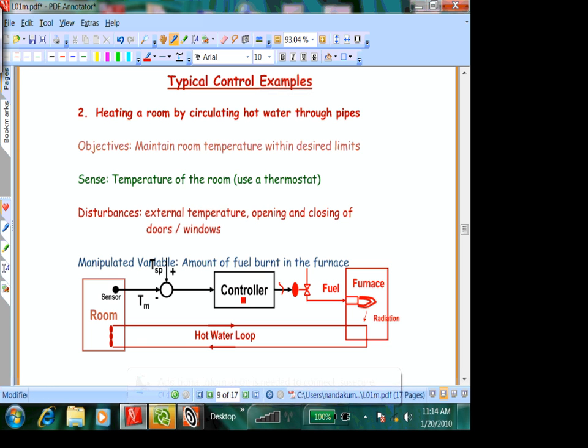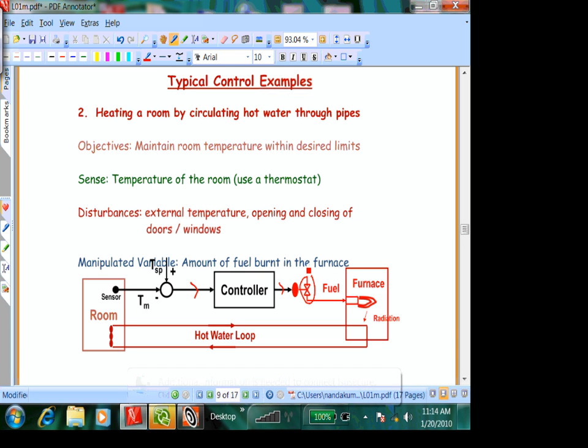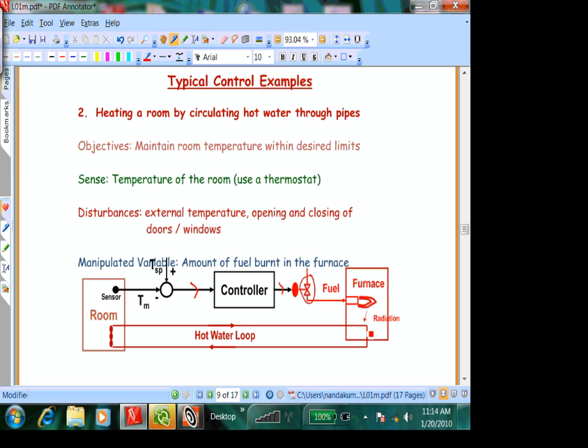These signals could be voltage coming in, and what comes out is so many BTUs per hour. So the controller figures out that a voltage of 5 millivolts corresponds to a temperature difference of 3 degrees, and it does the calculation using the process model and says, okay, I need to send 500 BTU per hour to bring back the temperature by that 3 degrees. So that action goes to a control valve. That means you need to increase the fuel rate. You need to burn more fuel. That will also have its own dynamics. Then the fuel goes into the furnace, and in this case you have a hot water loop. So the hot water temperature goes up, and the heat is delivered to the room. That completes the cycle. So this is why it's called a feedback loop.